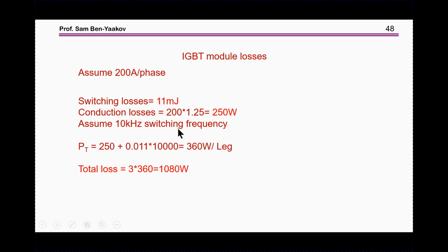I'm talking about a 400 volt line, and switching frequency of 10 kilohertz, which is okay for a motor. There's no advantage in feeding very high frequencies to modulate the inverter, because the losses when you feed a modulated signal to a motor will be very high at high frequency. 10 up to say 50 kilohertz is at most you'd like to go with today's motor.